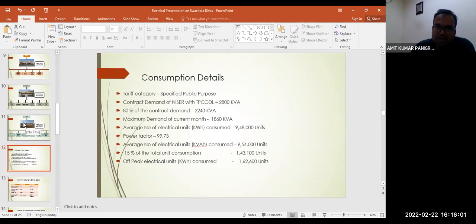So what are the consumption details? For the power supply from TPCODL, as per the contract, we come under specified public purpose because we are an educational institute. Though we get HT supply at 33 kV, we are charged at a lower rate than industries, because we are not a profit-making organization. Our contract demand with TPCODL is 2800 kVA. It is the maximum demand. Up to 2800 kVA at any point of time we can take power from the grid.